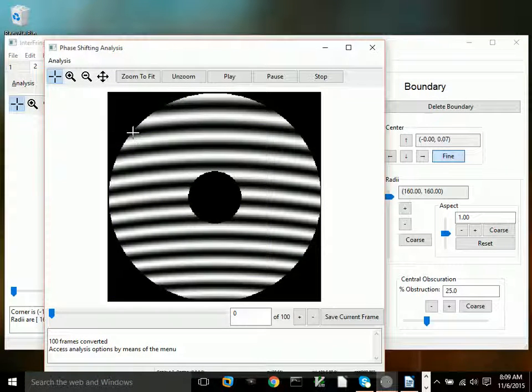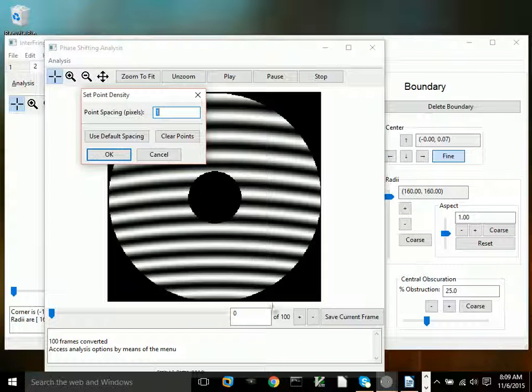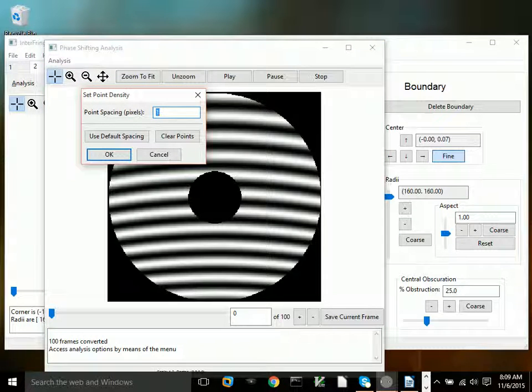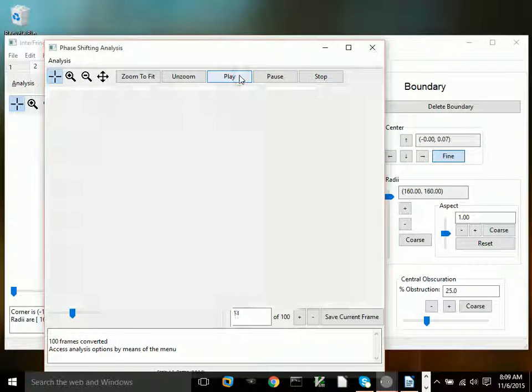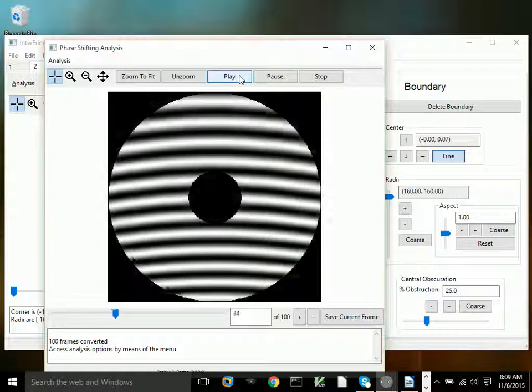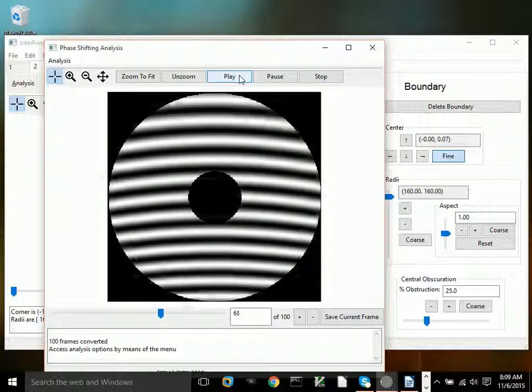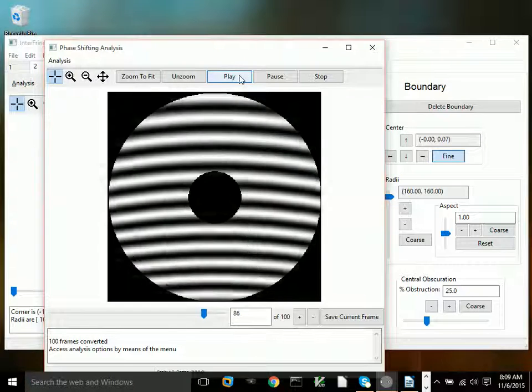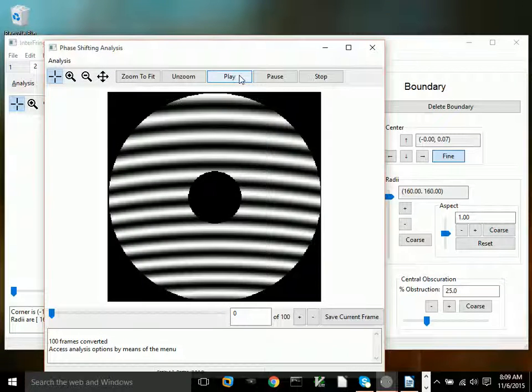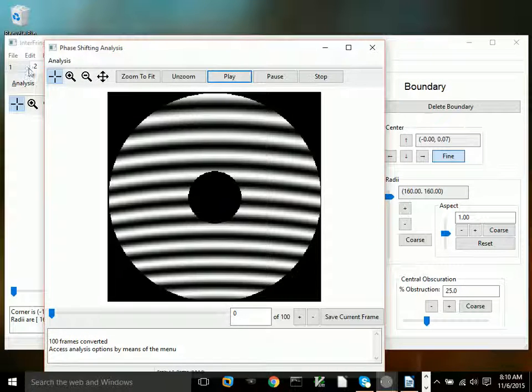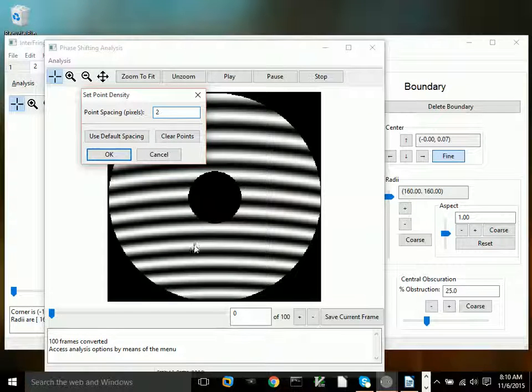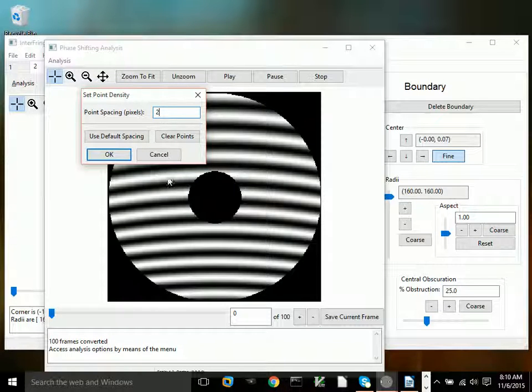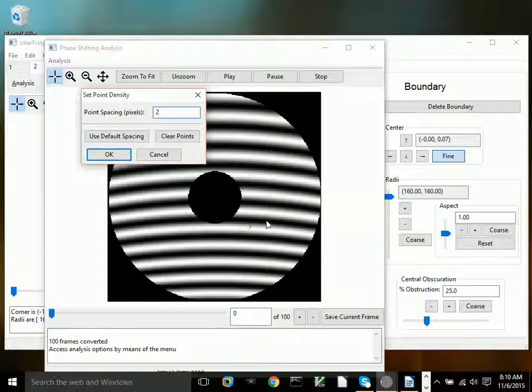Alright, we get the phase shifting analysis window open again, and we'll set the point density. There are 100 frames in this video. You can see what it looks like. It's gone through about three cycles of the fringe pattern. So we'll set the point density again at two pixels. That parameter should be verified using coarser spacing until it's clear that the resolution or the result is not changing with finer spacing.